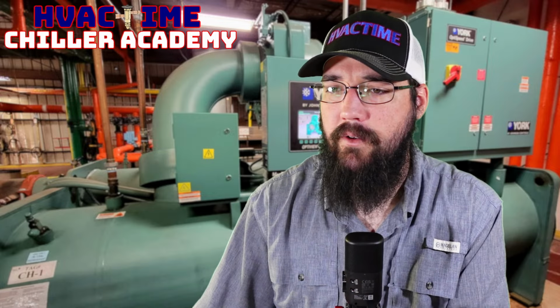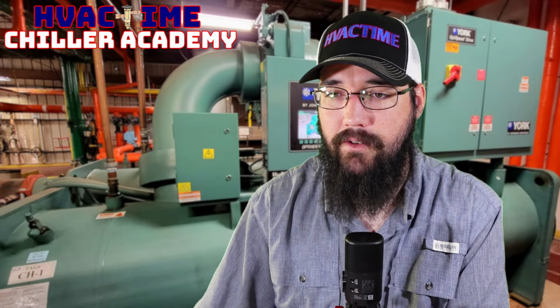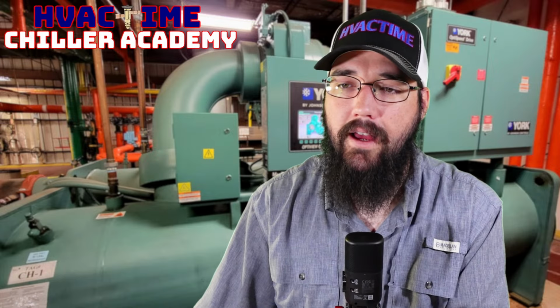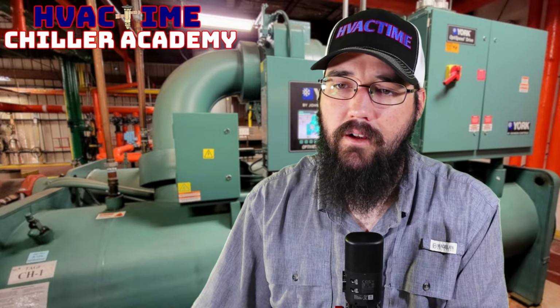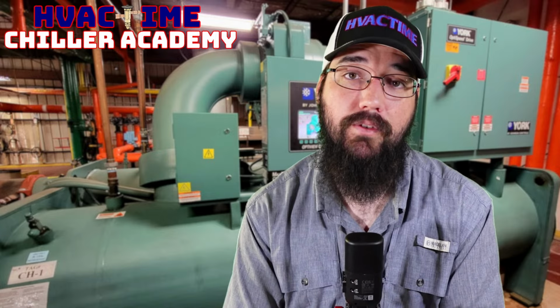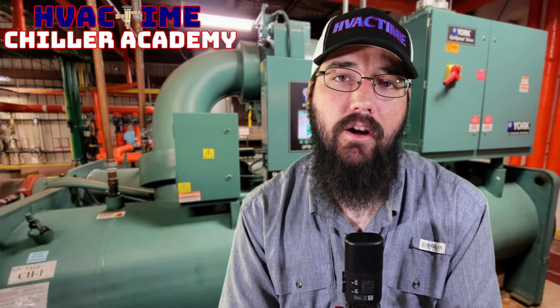All right. Do you have any training coming up for the Carrier 19 series centrifugals? And the trainings I have, so there's two main trainings I have right now, Albert. The first training is my certification course on chilleracademy.com. It's a self-paced course. Now, it's not specific on 19XR centrifugals, but what it does do is teach you all the same fundamentals that a 19XR does. Carrier centrifugals use a similar design theology to a York centrifugal with a low and high speed. So they have a low speed motor with a high speed impeller, or impellers, depending on if it's multi-stage.